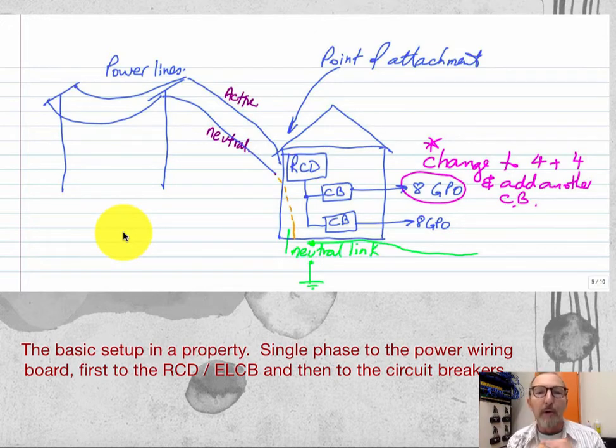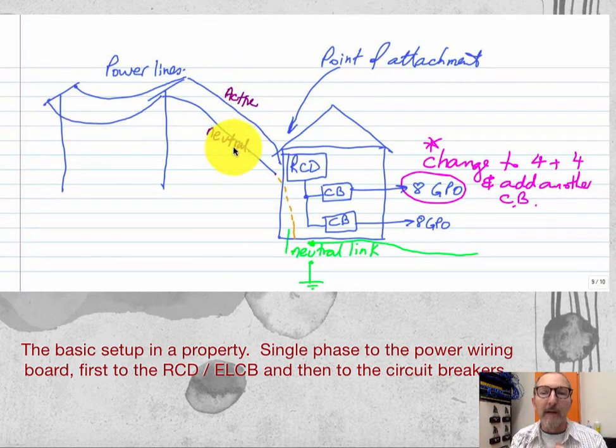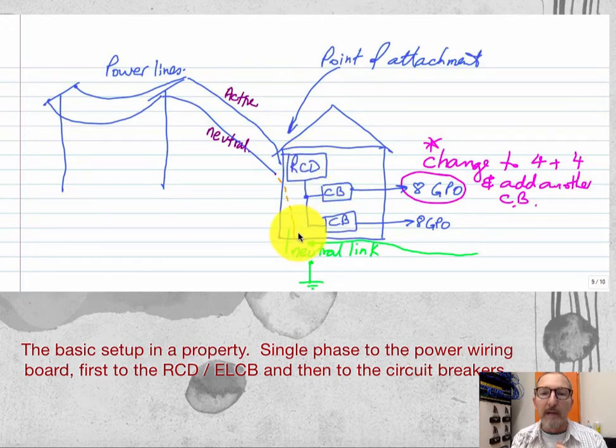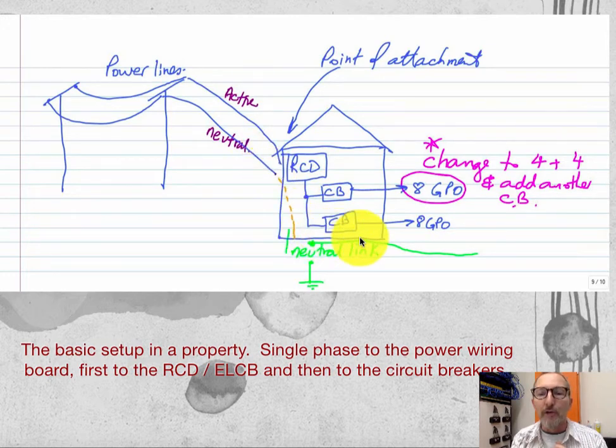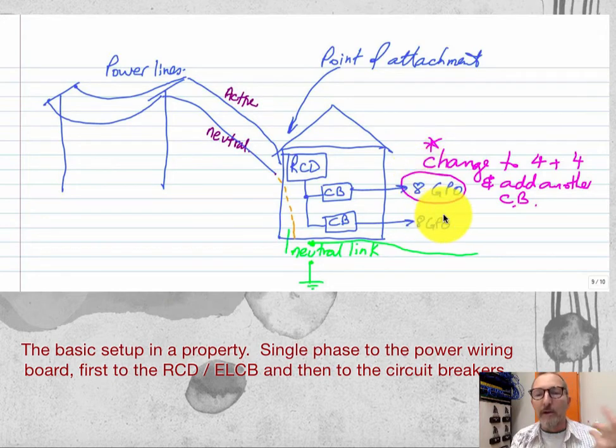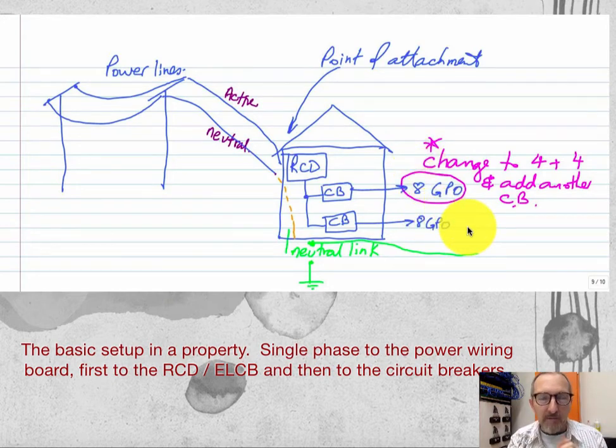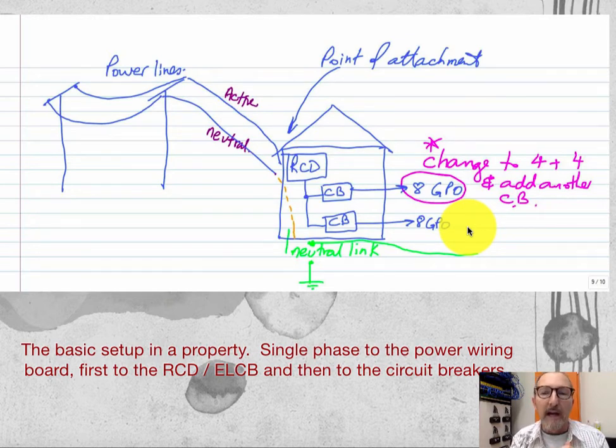Here's the basic setup for a property. We have the power lines with the active and neutral coming in, we have the RCD, we have several circuit breakers following the RCD, we have a neutral link in the power board which connects neutral to the ground in the house, and we have several GPOs on different circuits — all regulated by the AS3000 and the current rules at the time.